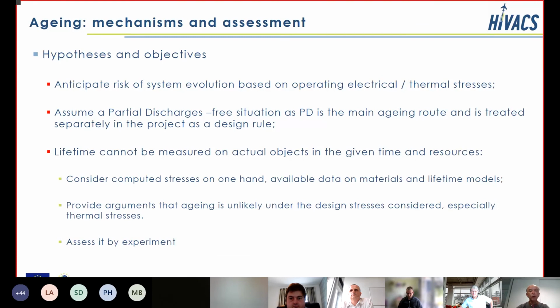So first, on the hypotheses and objectives. We want to anticipate the risk of a system evolution based on the operating electrical and thermal stresses. We have worked assuming a partial discharge-free situation in the initial state, because everything concerning PD occurrence was used as a criterion for the initial design rules. Within the time frame of the project, we couldn't make lifetime estimations. So what we did is that we considered the computed stresses on one end and the available data on materials that we can find. We provided some arguments that aging cannot occur at the design stress that we fixed, and we also assessed the thermal aspects by experiments.